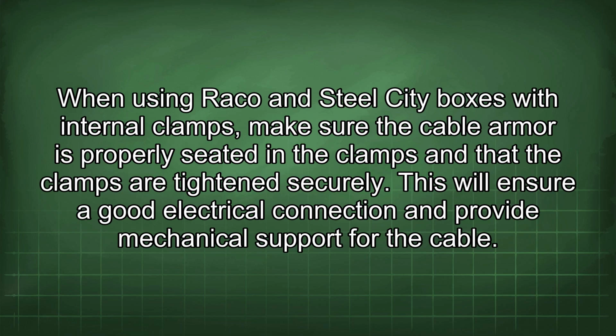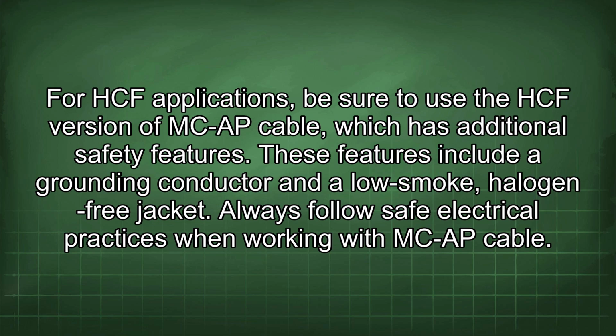When using Raco and Steel City boxes with internal clamps, make sure the cable armor is properly seated in the clamps and that the clamps are tightened securely. This will ensure a good electrical connection and provide mechanical support for the cable. For HCF applications, be sure to use the HCF version of MCAP cable, which has additional safety features. These features include a grounding conductor and a low-smoke, halogen-free jacket.